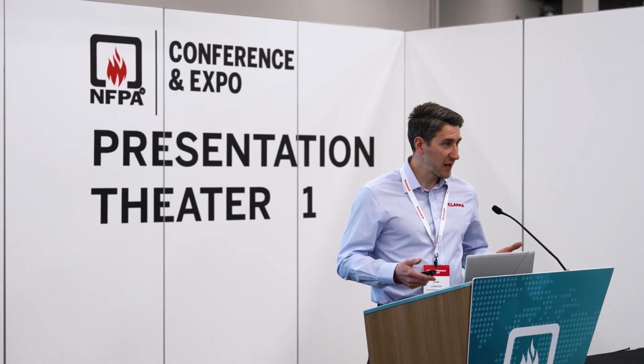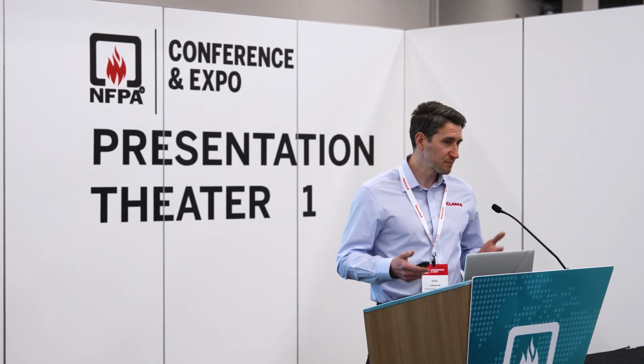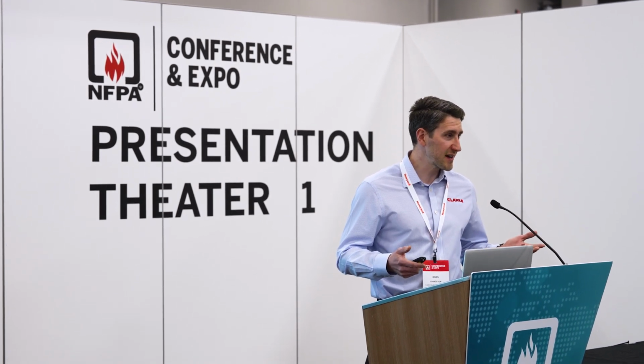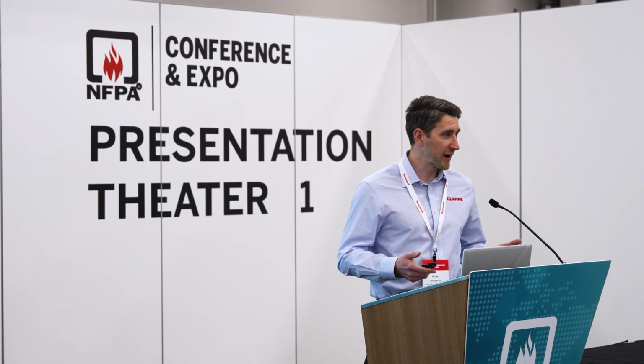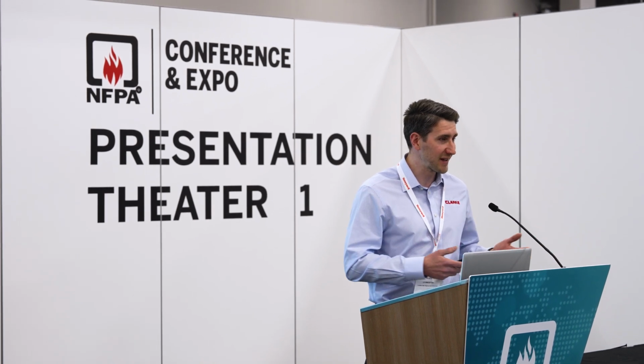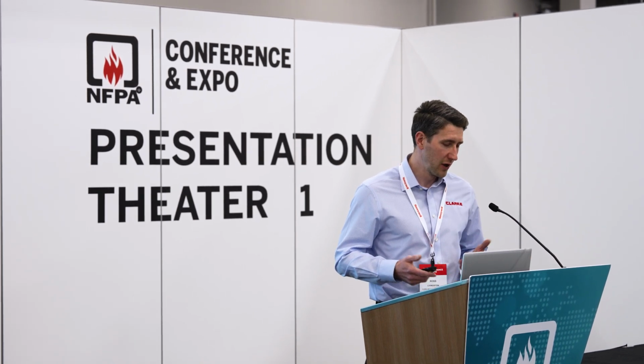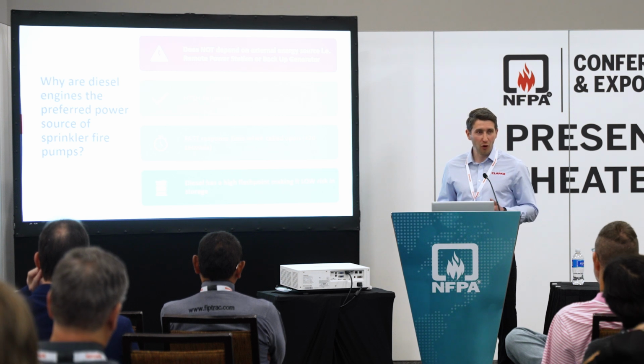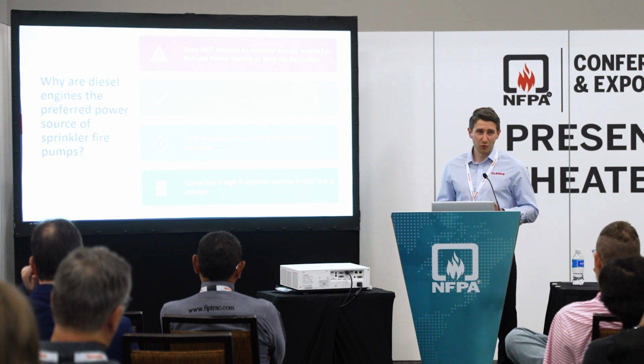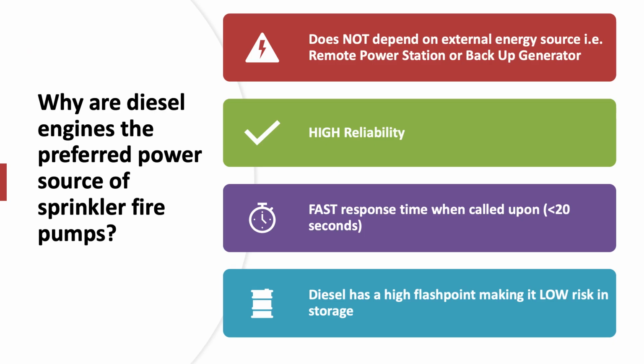When the fire department arrives, they could kill the power to the building. You might have an emergency genset, and hopefully it's been sized correctly for both the building's lighting and starting the fire pump, but we know from travelling the world that often isn't the case. So from an insurance perspective, diesel fire pumps are still considered the lowest risk solution for a fire pump system, and we believe that will continue.